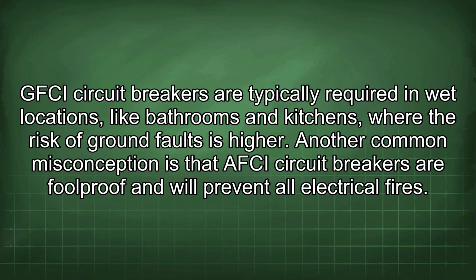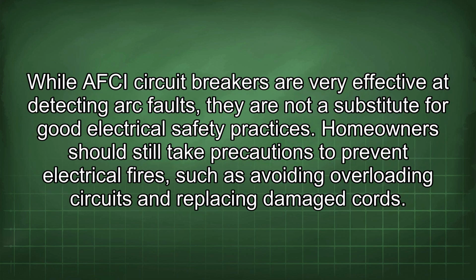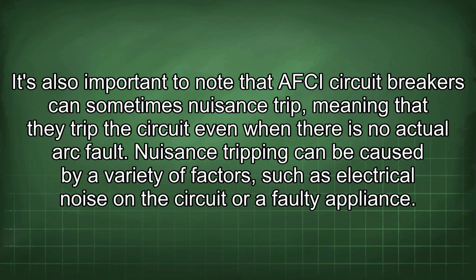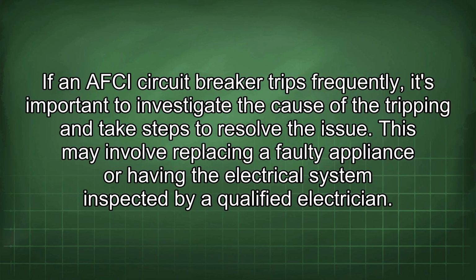Another common misconception is that AFCI circuit breakers are foolproof and will prevent all electrical fires. While AFCI circuit breakers are very effective at detecting arc faults, they are not a substitute for good electrical safety practices. Homeowners should still take precautions to prevent electrical fires, such as avoiding overloading circuits and replacing damaged cords. It's also important to note that AFCI circuit breakers can sometimes nuisance trip, meaning that they trip the circuit even when there is no actual arc fault. Nuisance tripping can be caused by a variety of factors, such as electrical noise in the circuit or a faulty appliance. If an AFCI circuit breaker trips frequently, it's important to investigate the cause of the tripping and take steps to resolve the issue. This may involve replacing a faulty appliance or having the electrical system inspected by a qualified electrician.